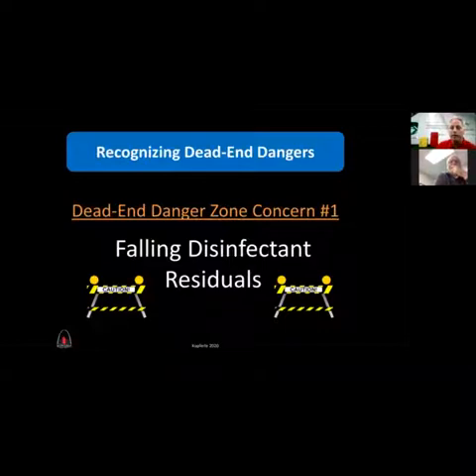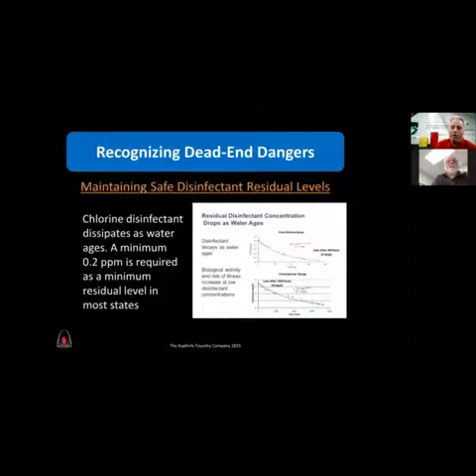This is something we'll probably start seeing spread in the US, where they'll hold compliance for a 0.2 ppm. When we add chlorine to water — just like in a swimming pool — chlorine dissipates over time. If you're using free chlorine, which the vast majority of systems use, free chlorine usually stays in the system pretty steady for about the first 200 hours, or about a week.